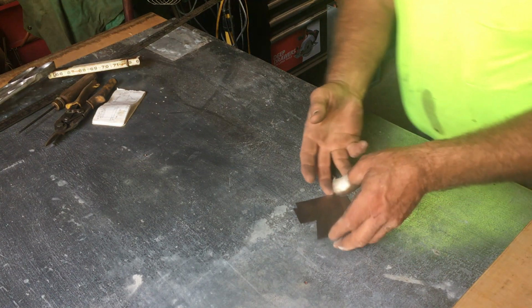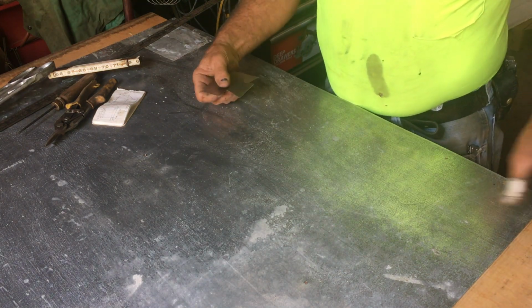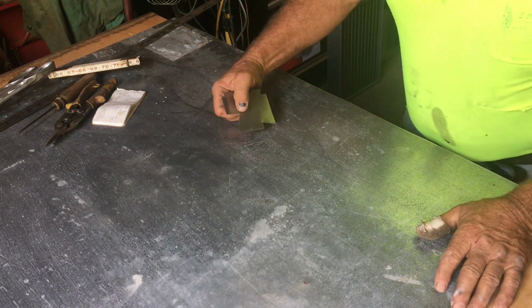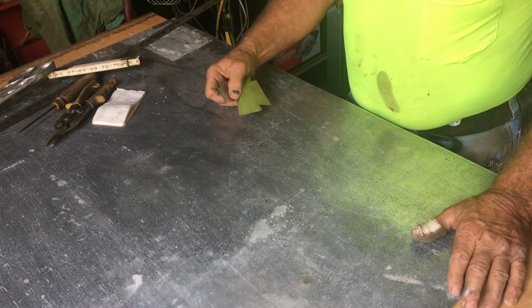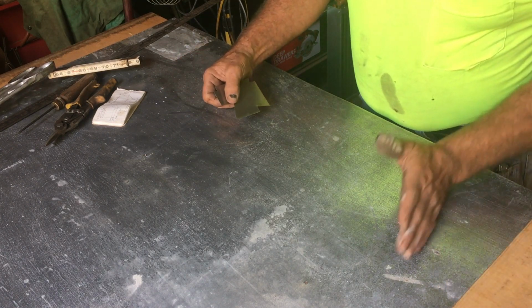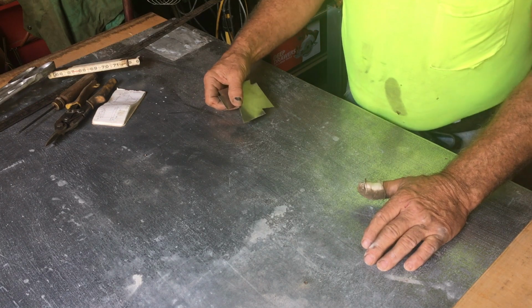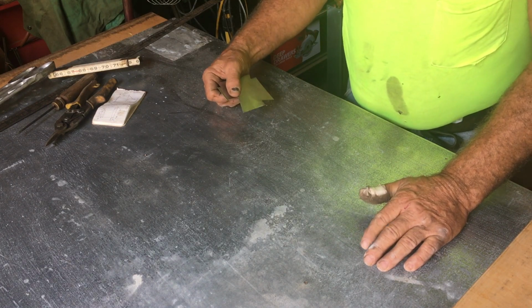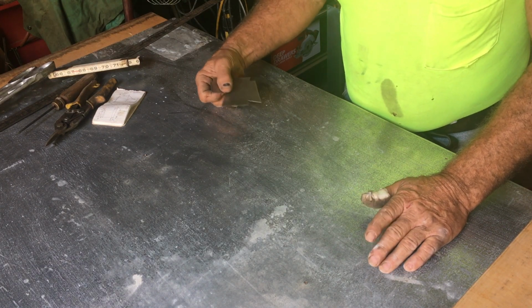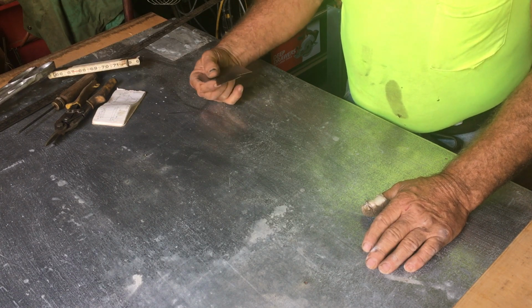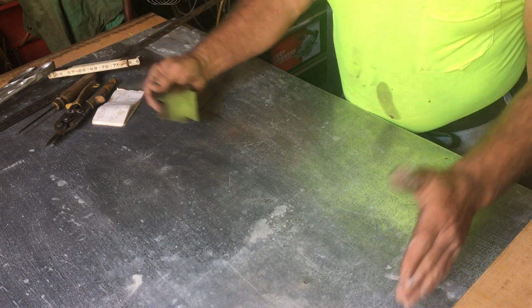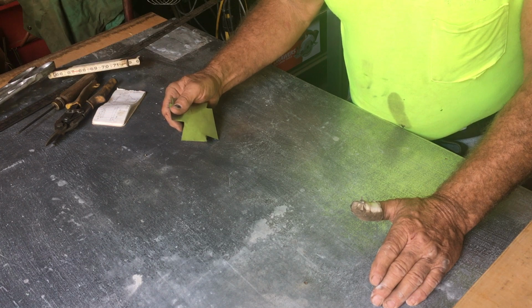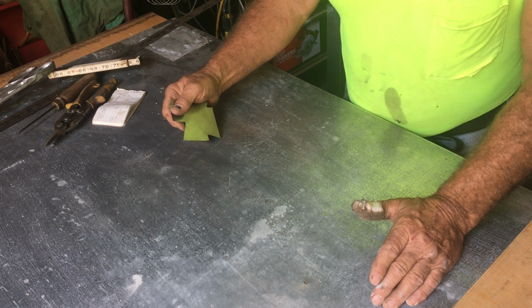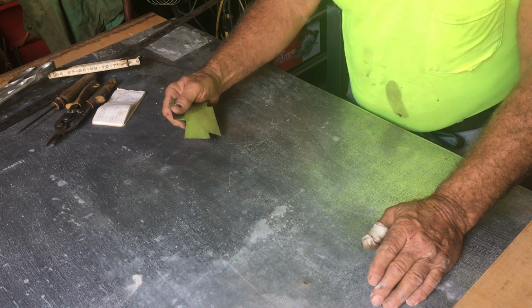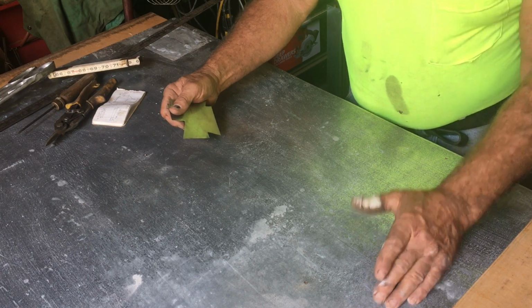Once you grab a piece of metal big enough to make what you want, or at least one portion of it, it's time to figure out how to lay it out. This particular seam is a locking seam called a Pittsburgh Lock, formed by a lock forming machine. It takes up 1 inch of material, so whatever dimension you add that lock to, you always have to add 1 inch to that dimension. But remember, we also talked about having a flange.